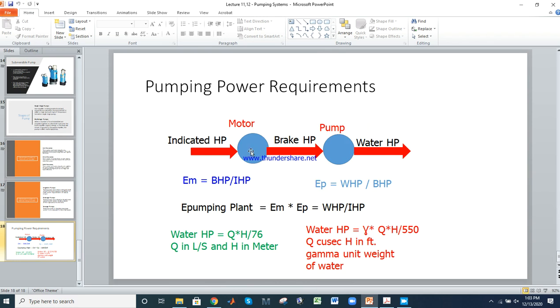Regarding pump efficiency: the motor is powered by indicated horsepower (IHP) as input, and the output is brake horsepower (BHP). The pump takes brake horsepower as input and outputs water horsepower (WHP). So: input horsepower is indicated horsepower, and output horsepower is water horsepower.